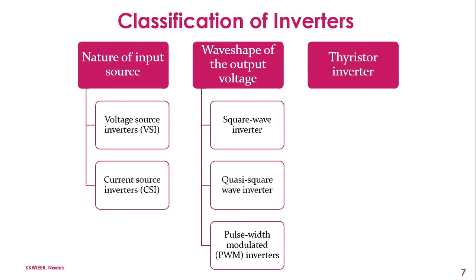So as we have seen before, a sinusoidal voltage or a sine wave output voltage is ideal for many high power applications. So this can be achieved by two methods, either by using filter circuit on the output side of inverter or using this method PWM, that is pulse width modulation, which uses a switching scheme within the inverter to modify the shape of output voltage waveform.